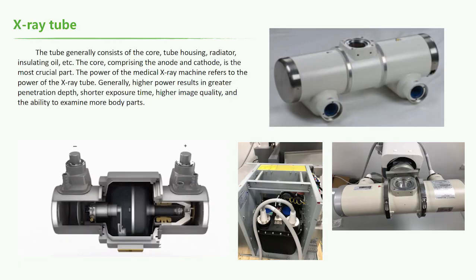The second part is an X-ray tube. The X-ray tube generally consists of the core, tube housing, radiator, insulating oil, etc. The core, comprising the anode and cathode, is the most crucial part. The power of the medical X-ray machine refers to the power of the X-ray tube. Generally, higher power results in a greater penetration depth, shorter exposure time, higher image quality, and the ability to examine more body parts.